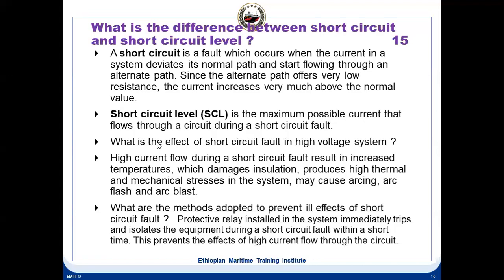What is the effect of a short circuit fault in a high voltage system? What happens in case of a short circuit in high voltage systems? Because of the higher current flow during a short circuit, it will result in increased temperature, which damages the insulation and produces high thermal and mechanical stresses in the system, and may cause arcing, arc flash and arc blast. We'll see what arc, arc flash and arc blast are. So you can understand that due to a short circuit there can be high temperature, and it can damage the insulation and cause thermal and mechanical stresses.